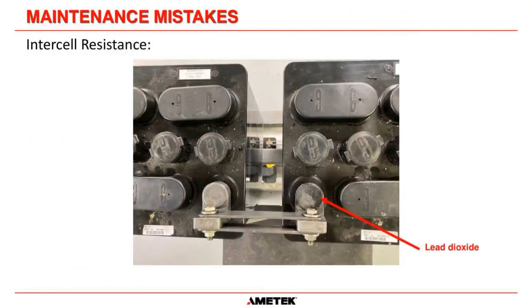What will degrade is this connection here. I've shown this arrow here - see this dark portion of the post? That's lead dioxide. What's happened here, this C&D cell has a crack somewhere in the jar post seal, and it's allowing electrolyte to wick or seep up through the connection. It's not supposed to be able to do this. When it does that on the positive post here, it's turning that lead into lead dioxide - it's kind of like a calcification layer.